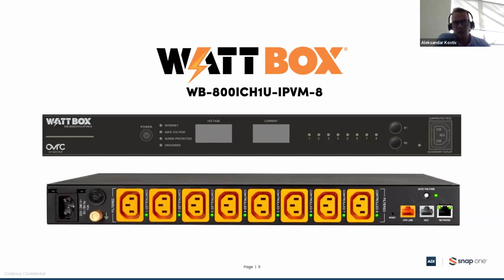Of course, if we speak about grounding, in that case we need to check the cable providing the main power to the WattBox itself, just to be sure that it is grounded properly. On the display, we have input voltage, which means we can see what is the voltage of our main electrical network.